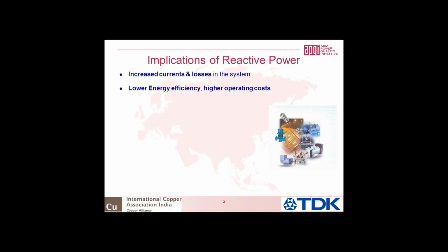And if you have increased losses in the system, you have lower energy efficiency, which means higher operating cost. Depending on the report you look at, the T&D losses could be anywhere between 8 to 30%, and that's a higher operating cost. And if you have a higher current, not only do you have a higher energy loss or lower energy efficiency, there's also blocked capacity. Because each of these pieces of equipment in the network, be it the cable, the conductor, the transformer, the switchgear, is rated to carry a certain current. And instead of carrying real current, if you're carrying reactive current, you're blocking the volt ampere capacity. For example, a 100 kVA transformer cannot deliver a 100 kilowatt load.